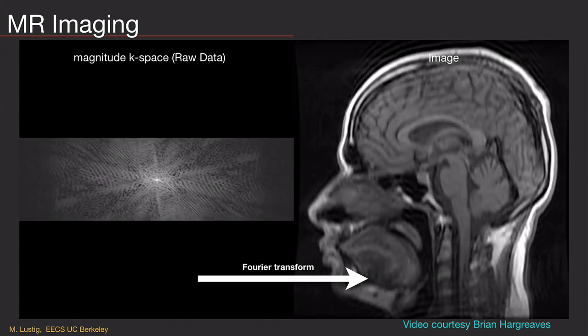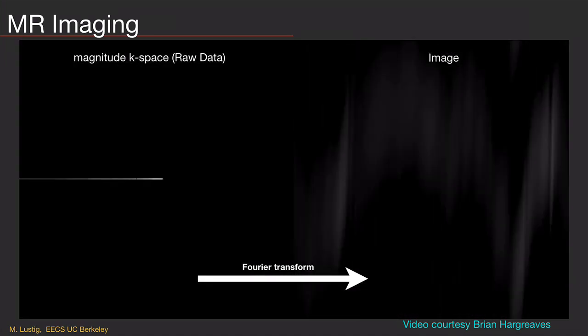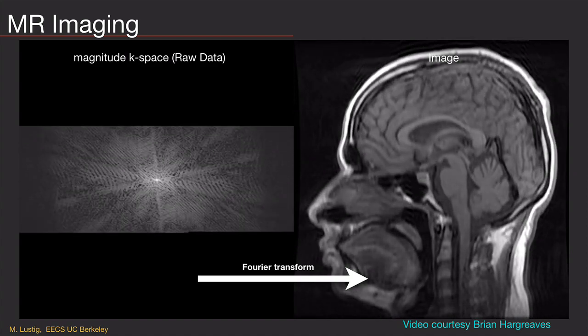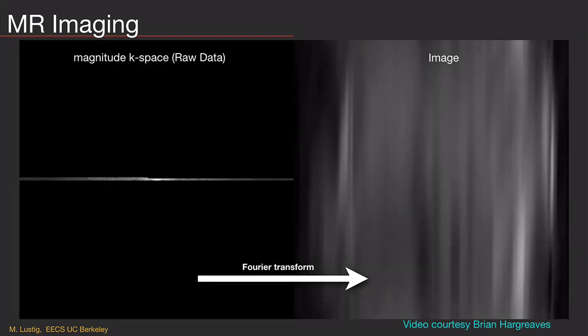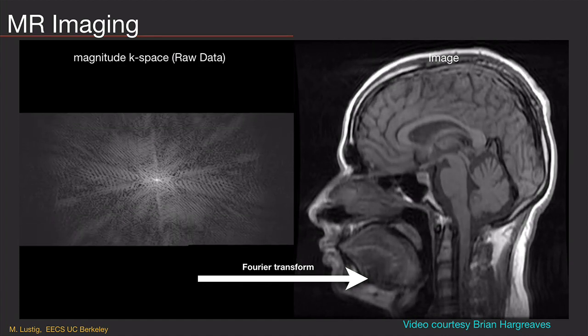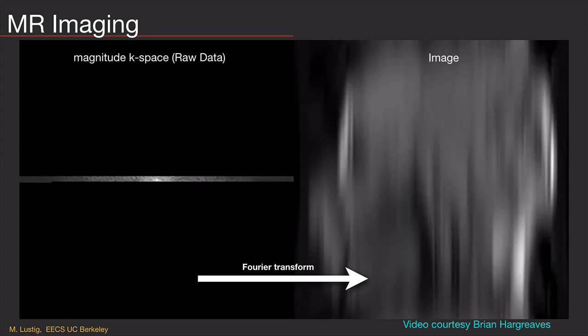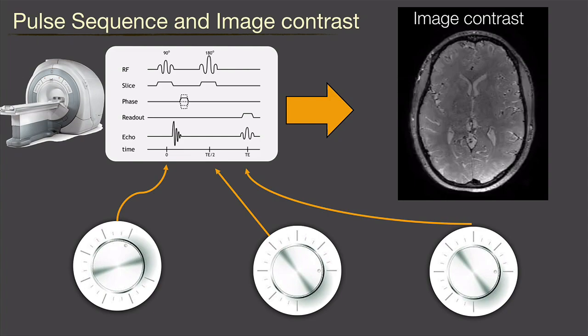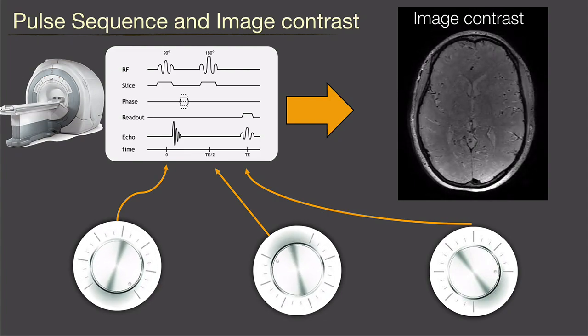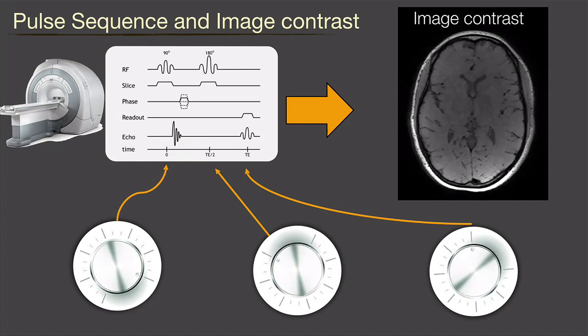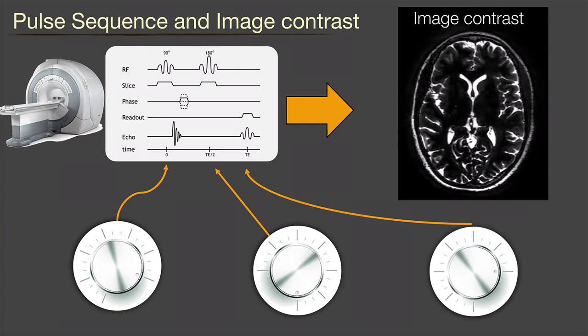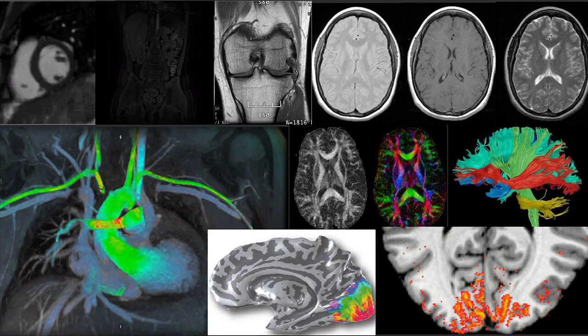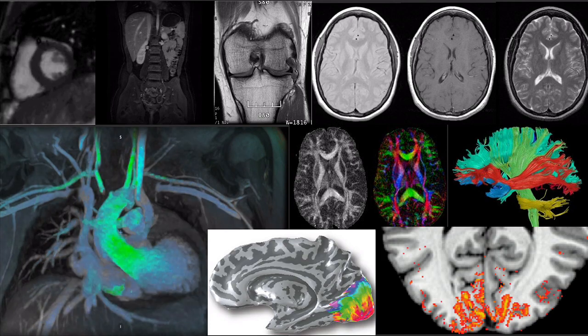This is the sound of MRI. MRI data is actually encoded — the raw data we get requires a Fourier transform, some transformation, in order to reconstruct images. The data is acquired sequentially, one after the other. To form an image, we need to collect data for a long time by repeating an experiment over and over. Once we have enough data, we can reconstruct an image — this is why MRI takes a long time. What's amazing about MRI is that you have all these knobs in a pulse sequence in the firmware, driving the magnetic fields, that can create various amazing contrast. Just changing sequence parameters in software, you can get completely different looking images. You can see extreme diversity of contrast — from structural to diffusion of water to functional and so on.